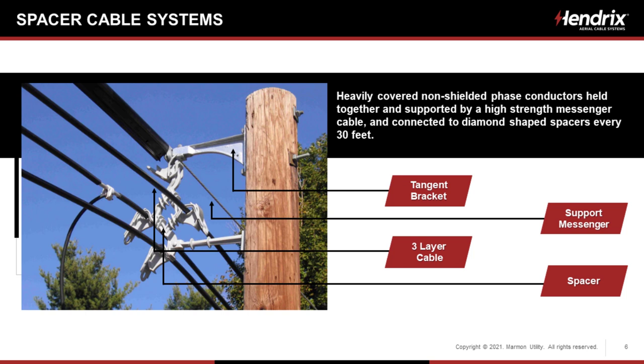Very briefly on theory or components, if you will, spacer cable is a heavily covered, non-shielded phase conductors held together and supported by a high-strength messenger cable. And you can see the messenger up there. It's got several functions. It's a mechanical support member. It holds everything up in the air. It's also your ground, your neutral, your lightning shield. And it also holds everything off that may fall on that bundle from up above.